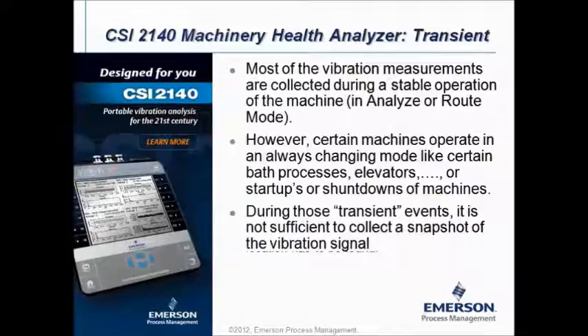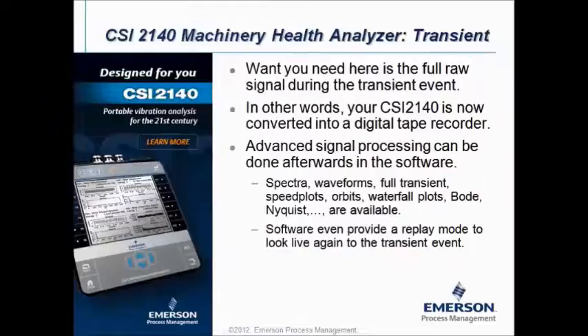However, certain machines operate in an always changing mode, like certain batch processes or elevators or startups or shutdowns of a machine. Now, if the conditions are changing all the time, we are calling that a transient event. And during a transient event, it is not sufficient to collect a snapshot of the vibration signal. What you need here is a full raw signal during the transient event. In other words, your CSI2140 is now converted into a digital tape recorder.